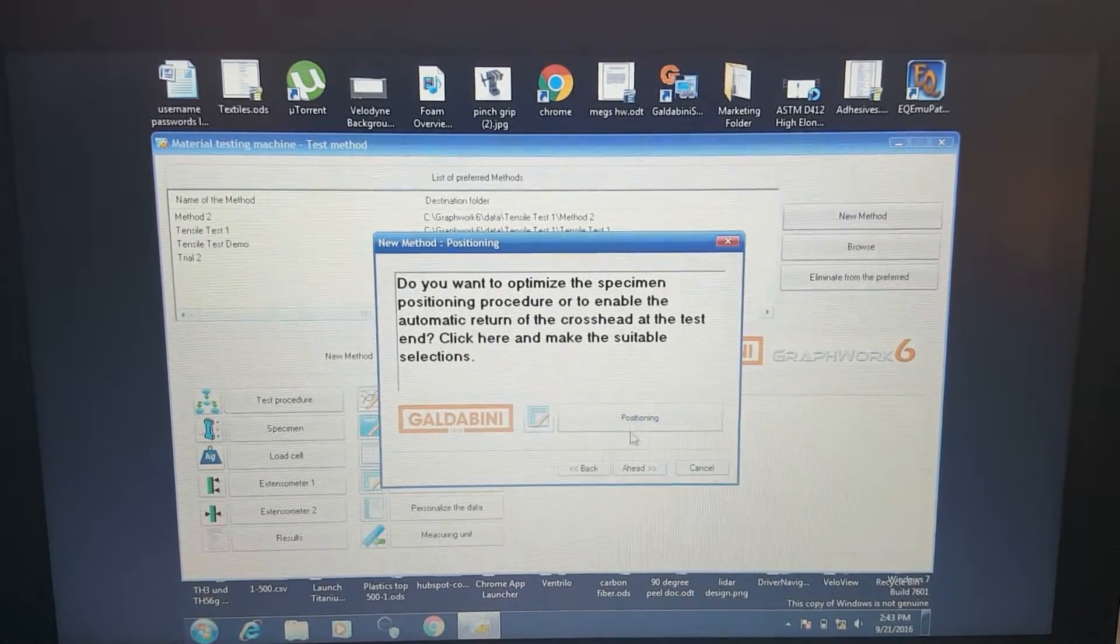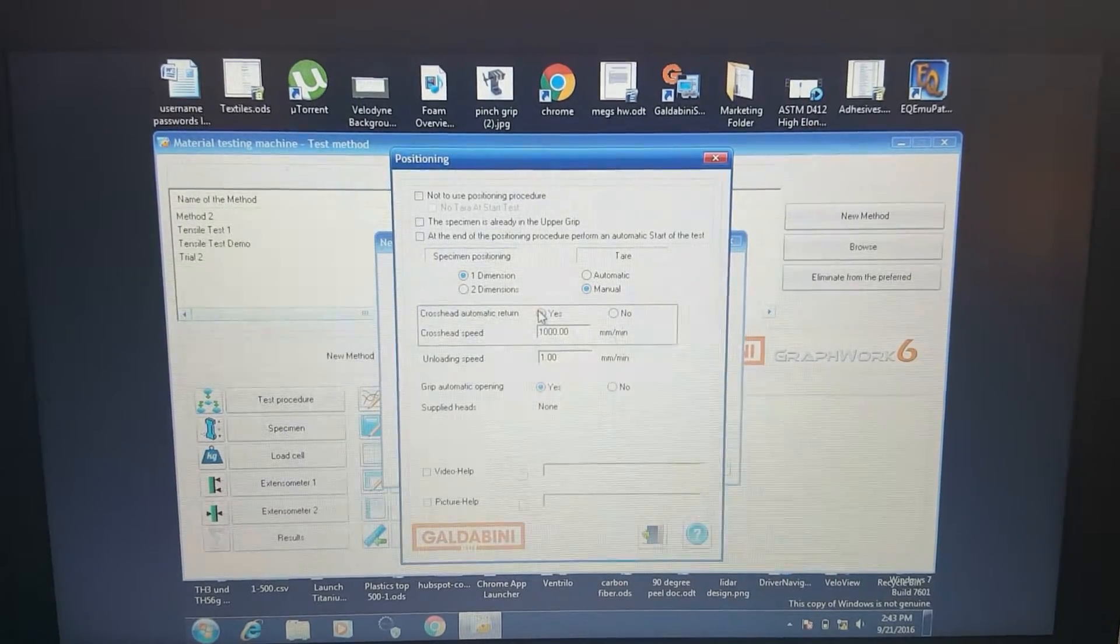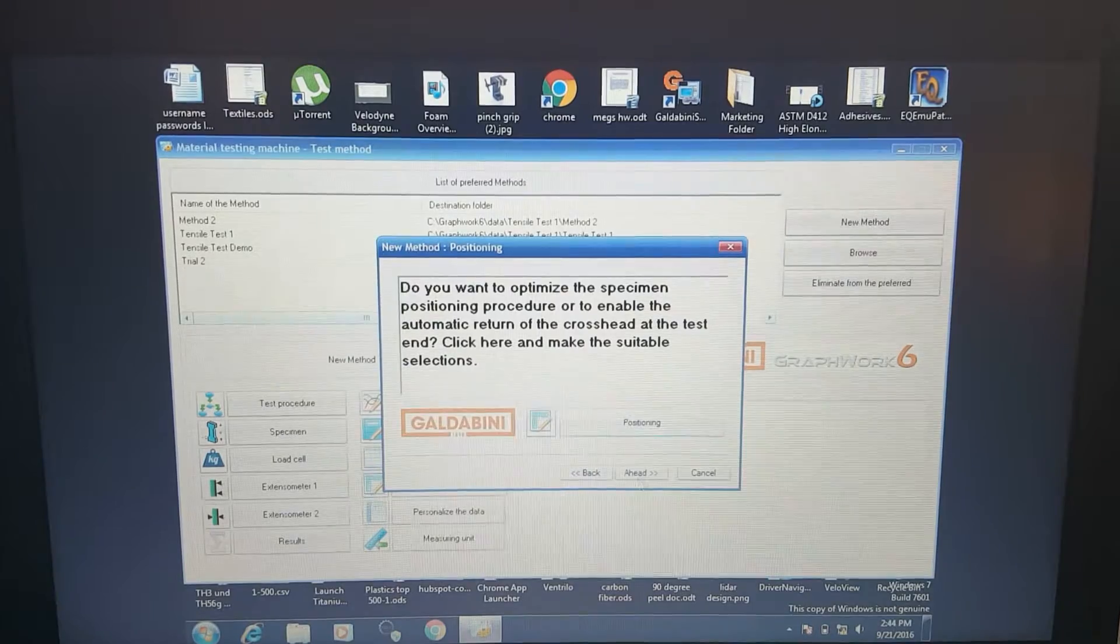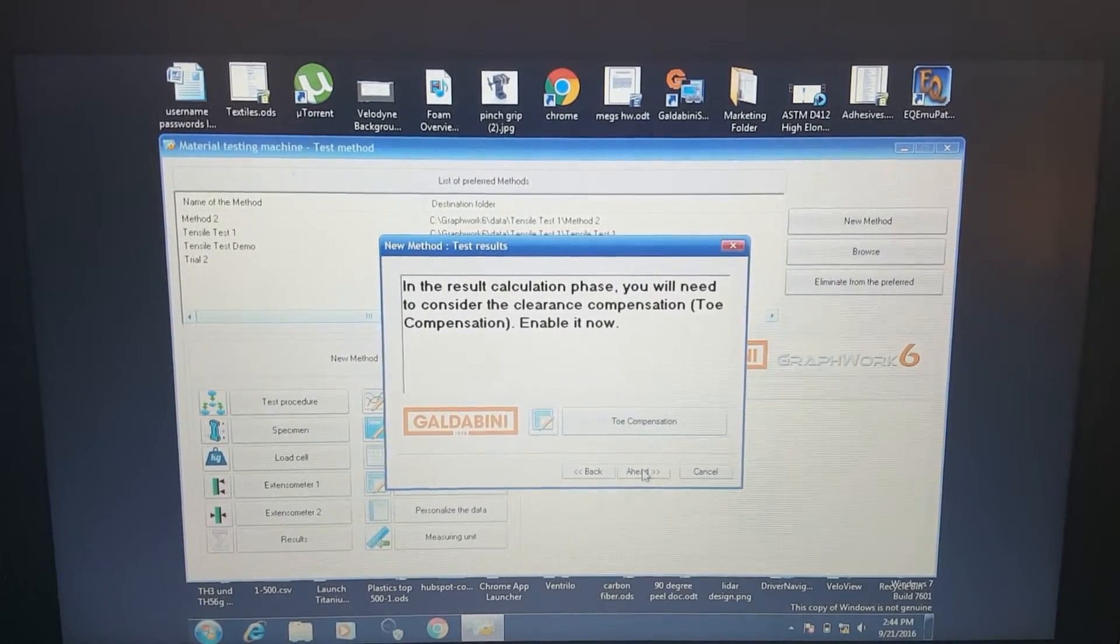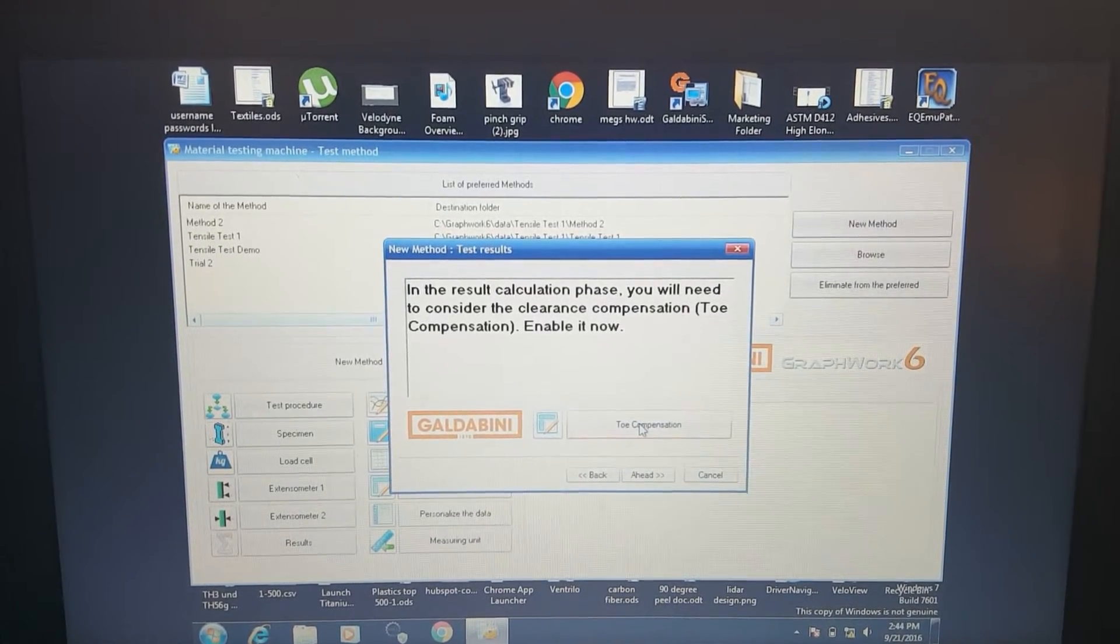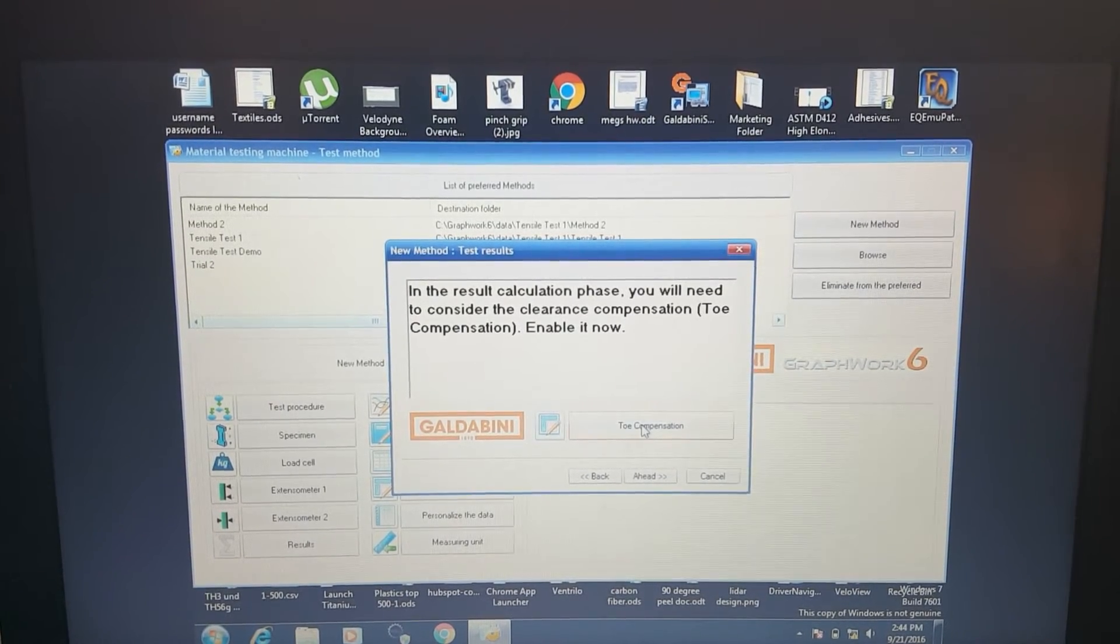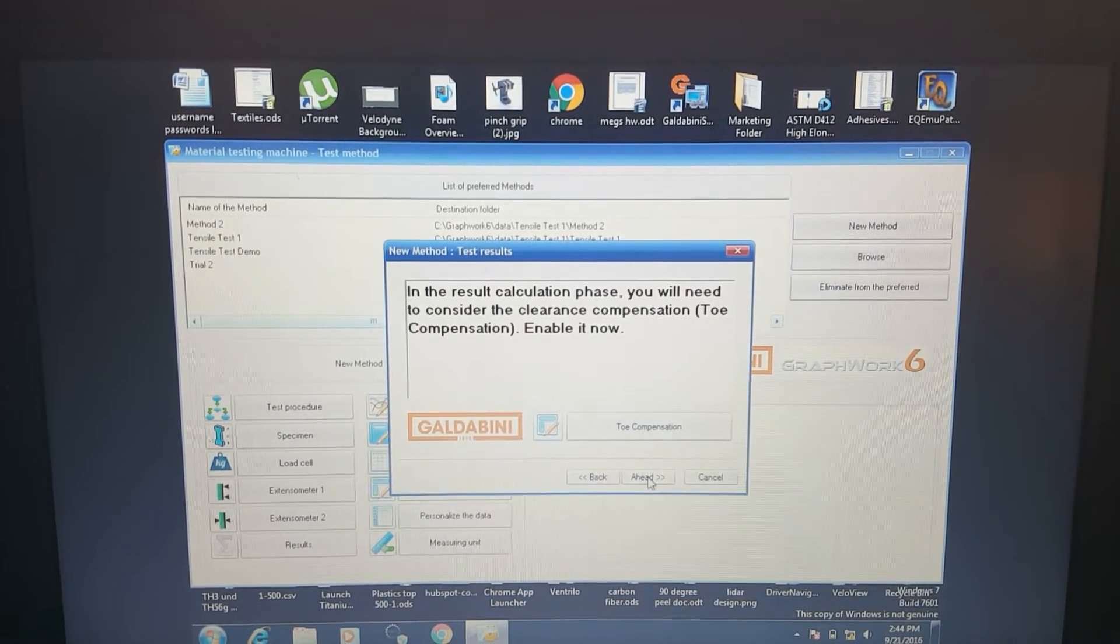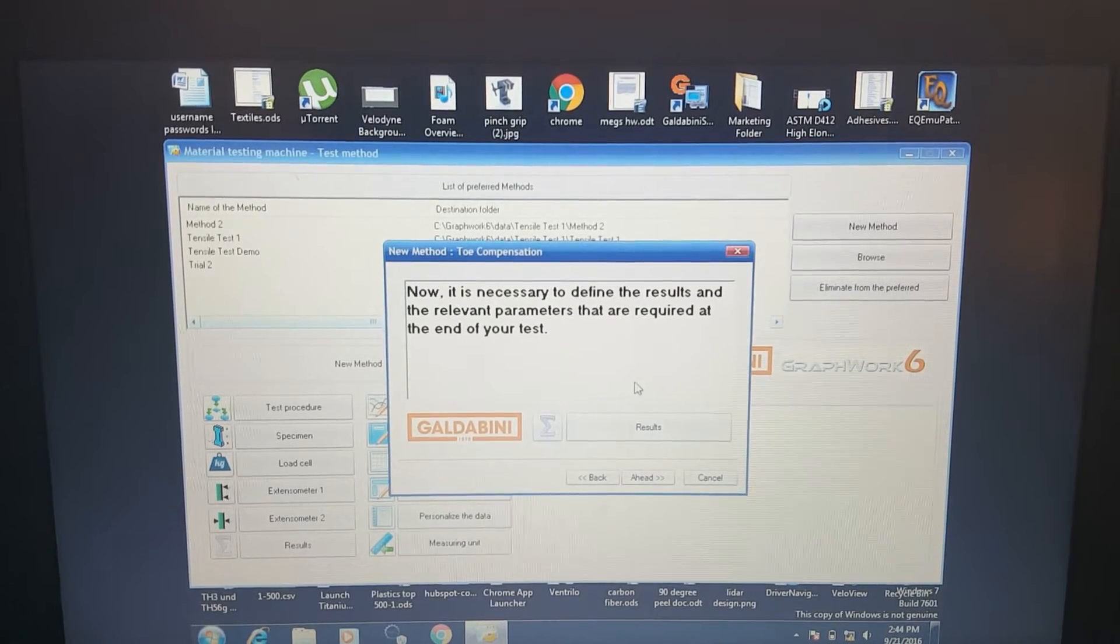This is if we want to return to home after the test. We want to do automatic return. Let's go with no. We don't need it for our purposes today, but it's nice if you're just running through a bunch of different samples. Toe compensation is for specific procedures that require toe compensation. It's basically the little bit of data at the start of the test, removing that data and just starting right when the tensile action occurs. We'll skip that for today, but that is a feature there if you need it.